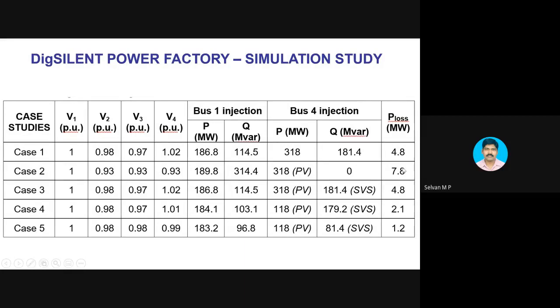The power loss has increased, so efficiency might have decreased. In order to tackle this, we need to have reactive power support at the buses where renewable energy integration is there. If I provide static var systems, SVS, which are capable of providing the same reactive power, then I will bring back the voltages again, and the loss comes back to the same value.